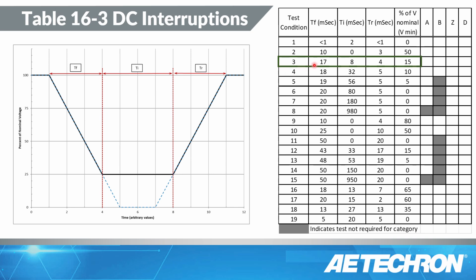So it has a fall time of 17 milliseconds. There's a dwell time at some minimum voltage for 8 milliseconds, and then a rise time for 4 milliseconds. The dwell time is not at 0. It's going to be at 15% of the nominal voltage. Well, for 28 volts, 15% is 4.2 volts. So the test should start here at 28 volts, fall for 17 milliseconds to 4.2 volts, dwell for 8 milliseconds at 4.2 volts, and then rise for 4 milliseconds back up to 28 volts.